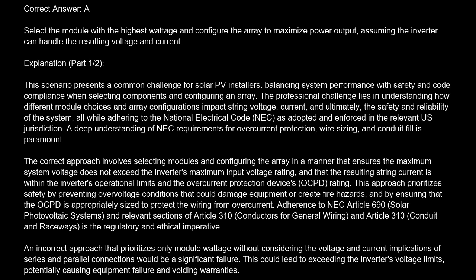The correct approach involves selecting modules and configuring the array in a manner that ensures the maximum system voltage does not exceed the inverter's maximum input voltage rating, and that the resulting string current is within the inverter's operational limits and the overcurrent protection device's OCPD rating. This approach prioritizes safety by preventing overvoltage conditions that could damage equipment or create fire hazards, and by ensuring that the OCPD is appropriately sized to protect the wiring from overcurrent. Adherence to NEC Article 690, Solar Photovoltaic Systems, and relevant sections of Article 310, Conductors for General Wiring, and Article 358, Conduit and Raceways, is the regulatory and ethical imperative. An incorrect approach that prioritizes only module wattage, without considering the voltage and current implications of series and parallel connections, would be a significant failure.